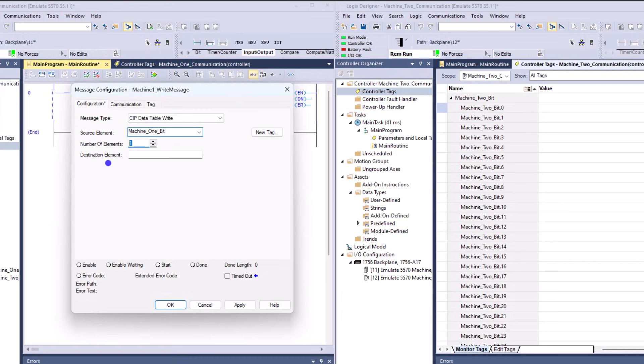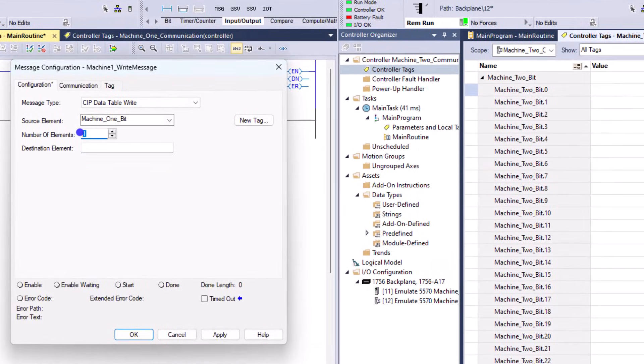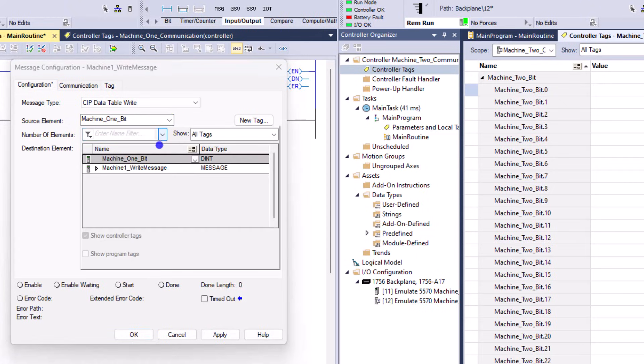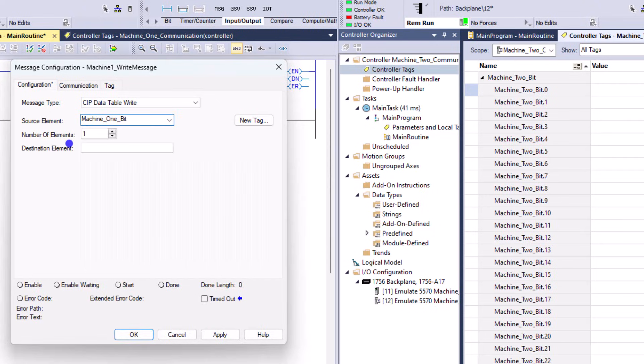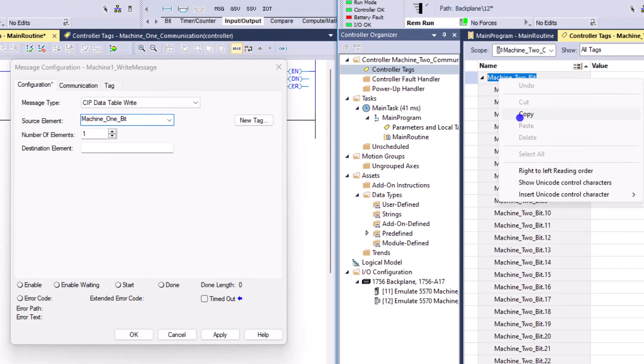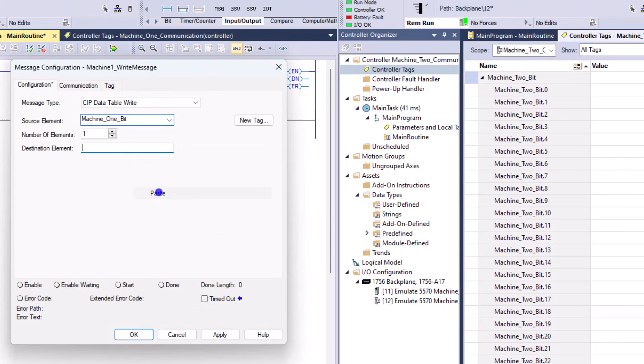We're going to put in the number of elements we'd like to transfer. Since it's a 32-bit DINT, we're going at the word level - the very top level - so we want to choose one element. If you started at bit one or bit two you would change the element size. The source element is from my first PLC - machine one. For the destination, I open my second machine - machine two - copy the tag, and paste it in the destination. Make sure source and destination are the same data type - that's very important.